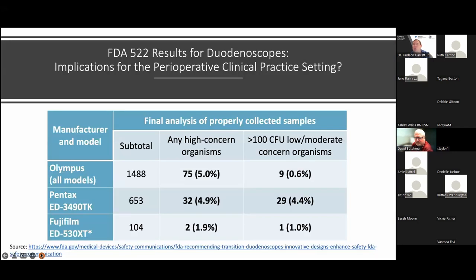So here are the results: almost 6%, and in some cases broken out by device you'd see upwards of 10%. The averages were about 5% for Olympus, 4.9% for Pentax, and 1.9% for Fuji. Keep in mind the sample size for Fuji is much smaller, which skews those statistics. But this was an alarming fact for the FDA to hear, because their expectation was that none of these devices would have anything harmful in them.